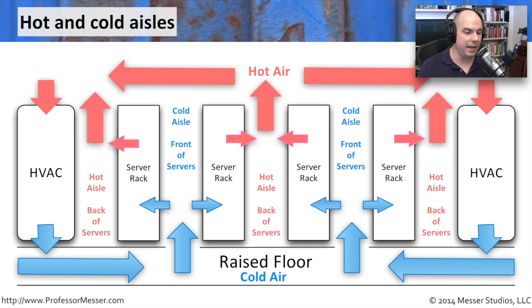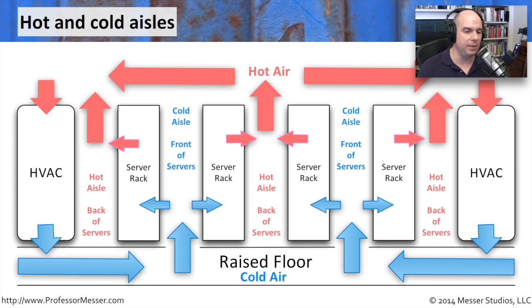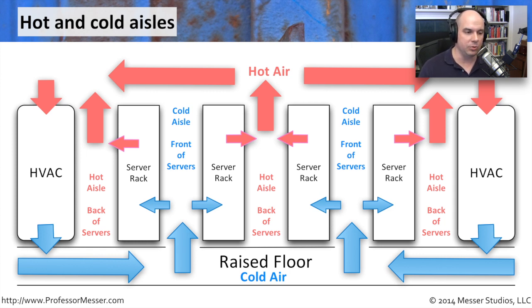Back-to-back aisles are our hot aisles — that's where all the hot air is coming out. It rises to the top of the building, where it will then be pulled back down through our air conditioning systems, cooled again, and sent back through the raised floor.